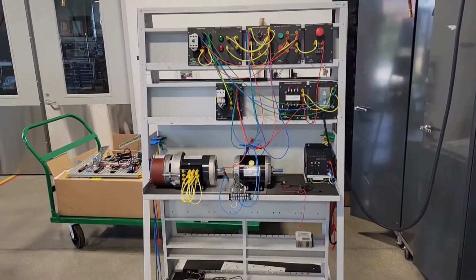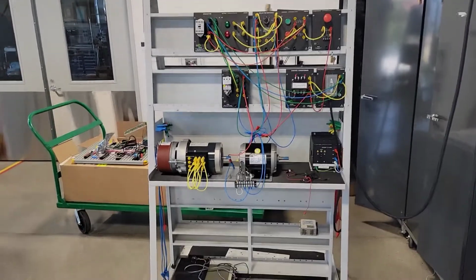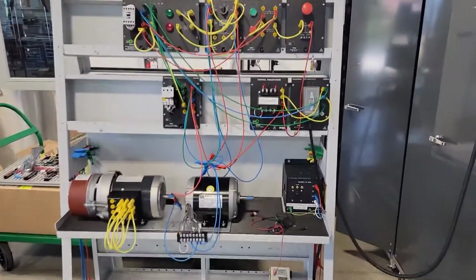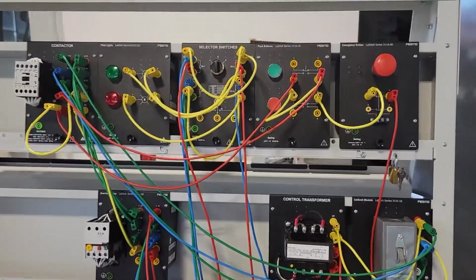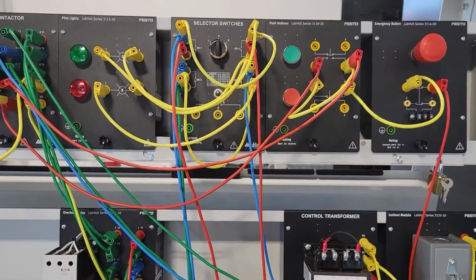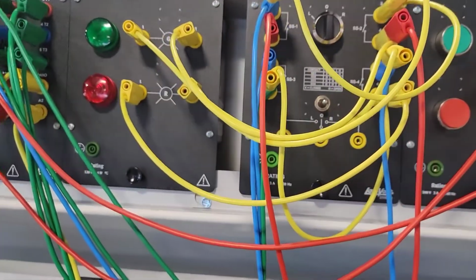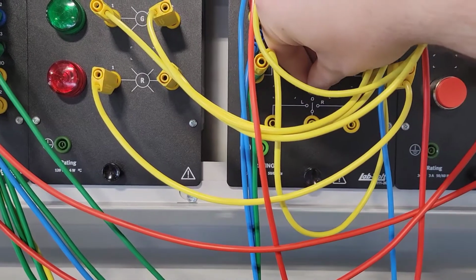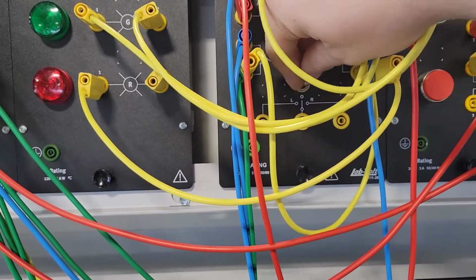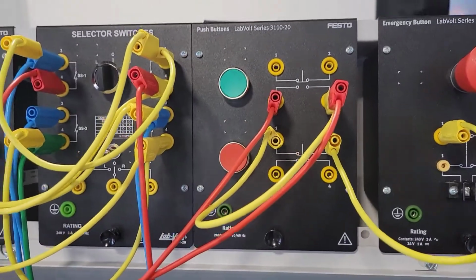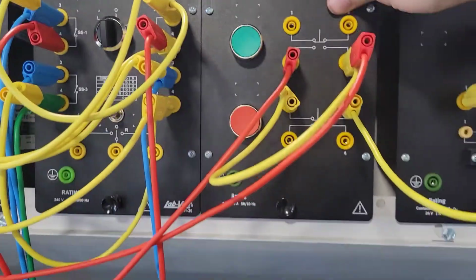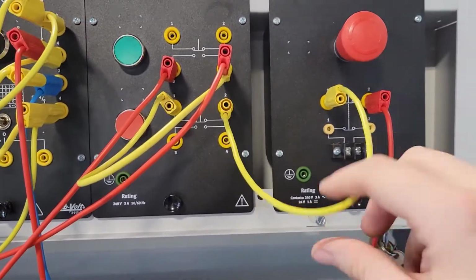MEC 130 Lab 3, this is a three-wire connection, so the system has remained relatively the same. The changes made were, instead of having a two-wire setup controlled by this switch down here, that has been swapped out for a push button. This push button is connected to the e-stop.